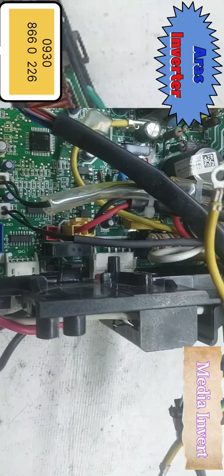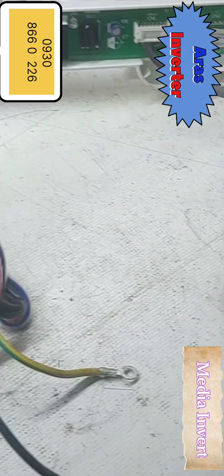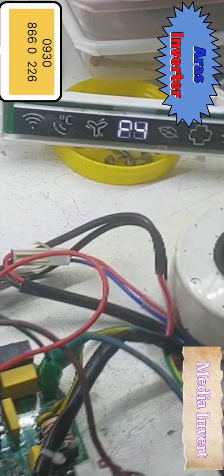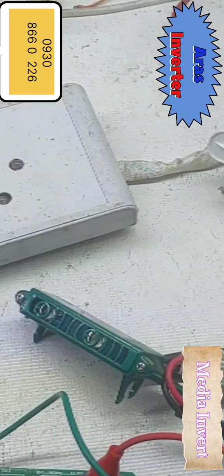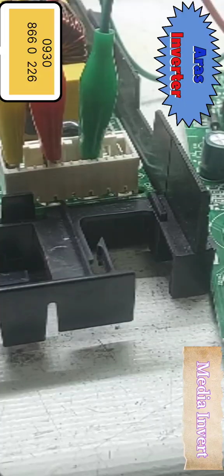This abnormal state can disrupt the communication signals between the indoor and outdoor units, causing the control system to also flag an E1 error. Conclusion: the primary fault is most likely related to the outdoor fan system, causing the P4 error. The E1 error is the probable secondary effect.